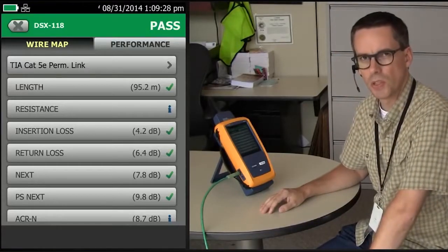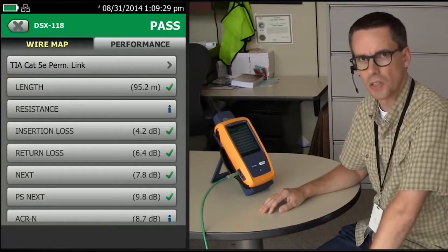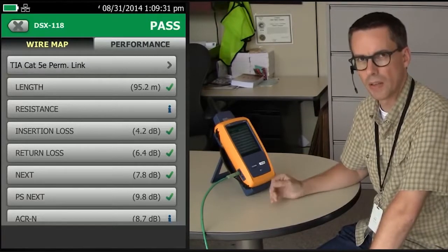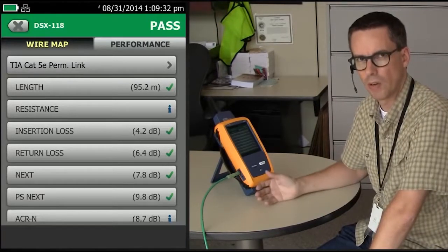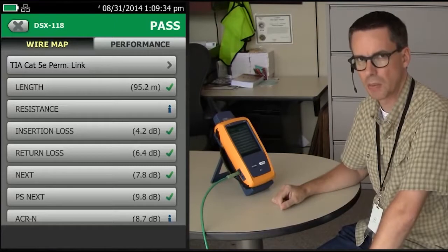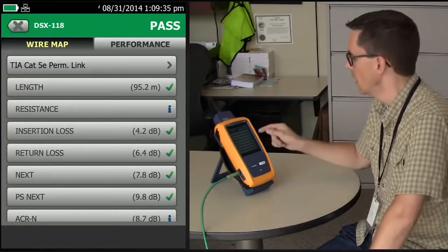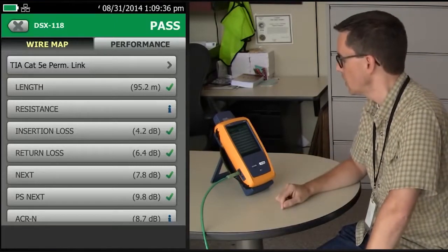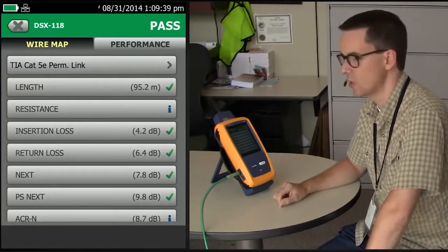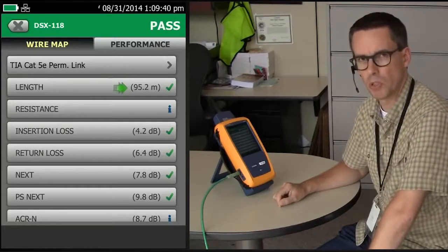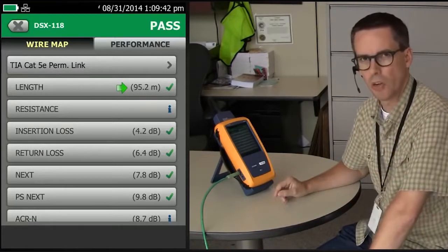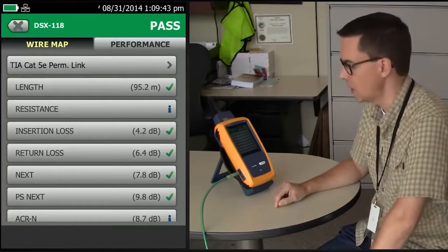One of the most common questions into the Technical Assistance Center is why the length did not fail on the tester when it exceeded the test limit. Let's take a look at the example here. The length reported was 95.2 meters, around about 312 feet.